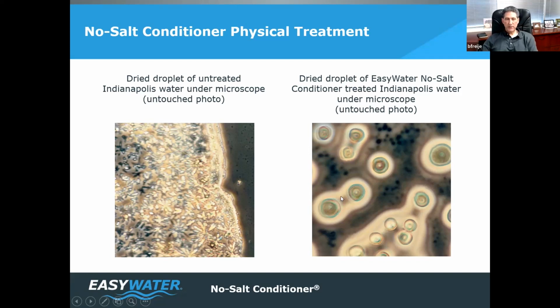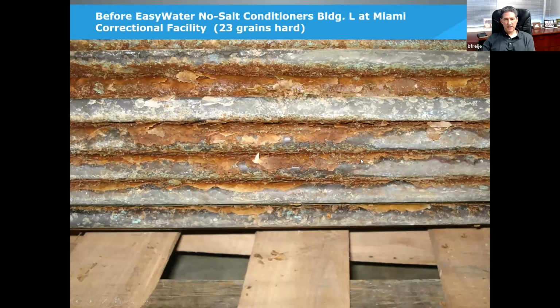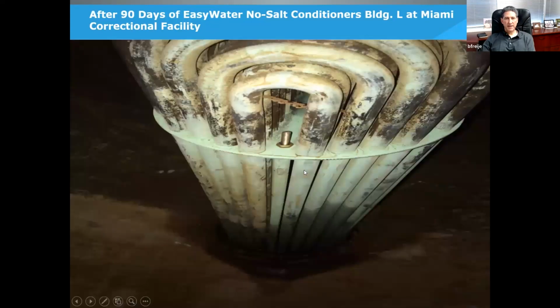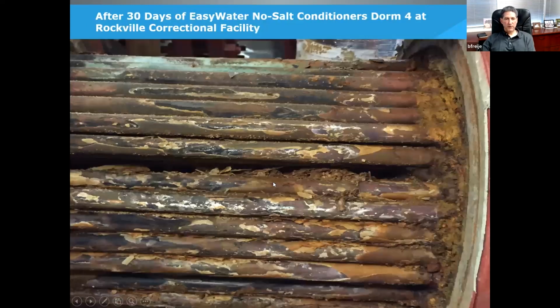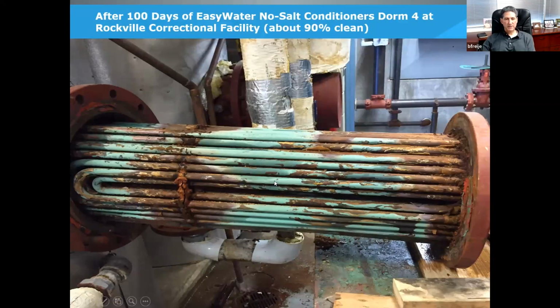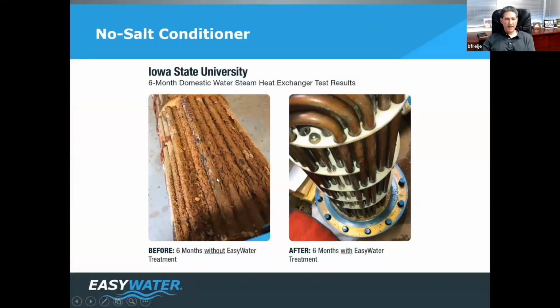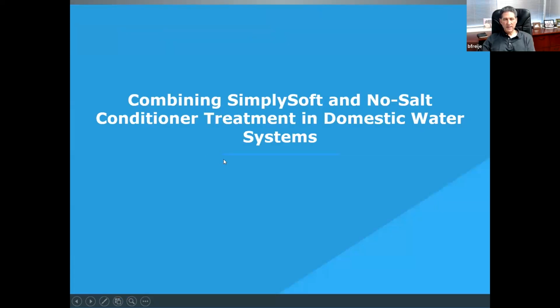And this treated water, on the right, can actually dissolve existing scale. So you can take a scaled-up domestic water heat exchanger - in 30 days, 90 days, completely free of scale. Another one, 30 days, 100 days, about 90% clean. Iowa State, horrible water, hard and high pH, 9.4 pH, high-rise dormitory, steam hot water, domestic water heating, 2 bundle - 6 months with treatment, 6 months without.